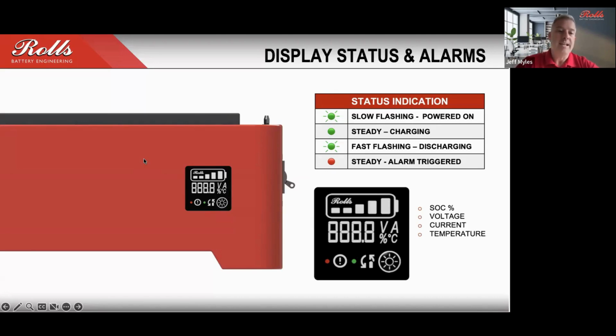We have an LFP Connect app, which allows you to connect to the batteries via Bluetooth. And once you connect to those batteries, you can actually see a fault log for that battery, and it will record any incidents where the alarm has been triggered, and will save that information in a data log. So if you do run into a situation where the battery is triggering an alarm condition and it's being recorded, you can look at that through the LFP Connect app.